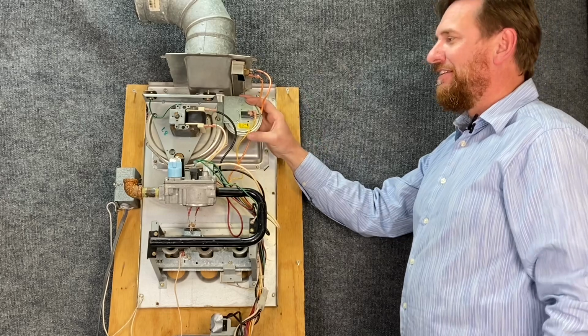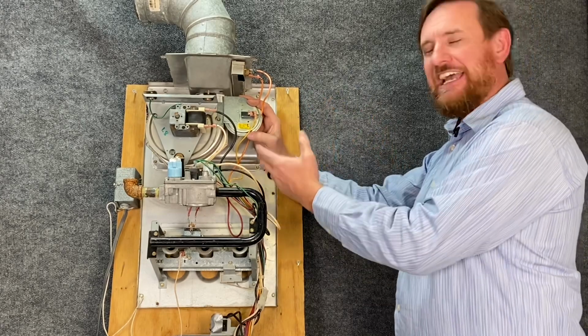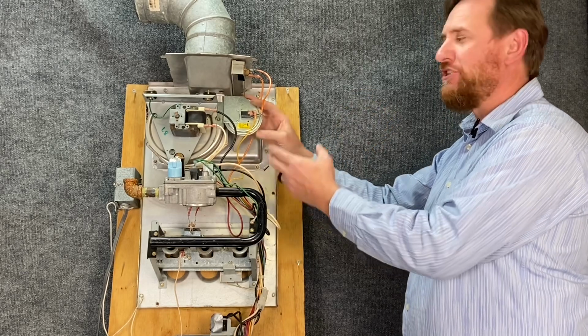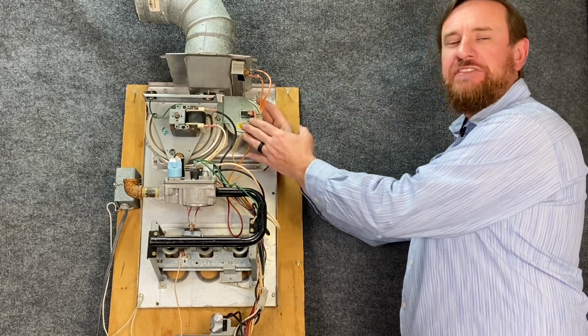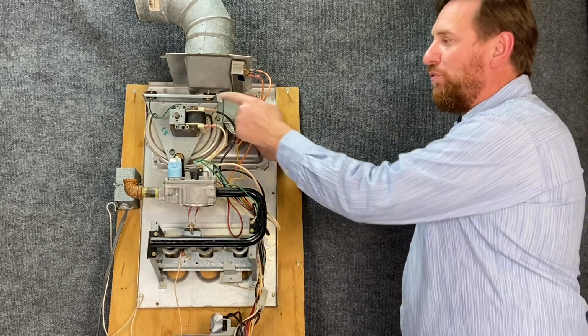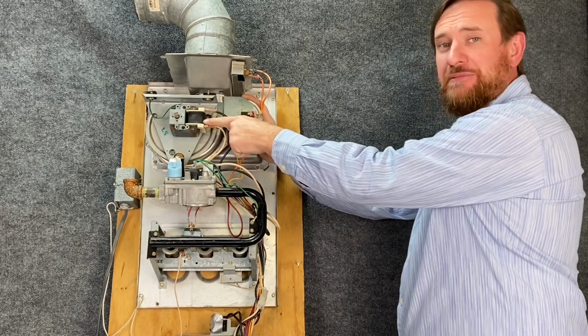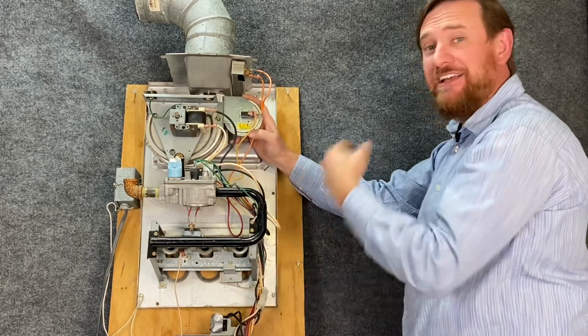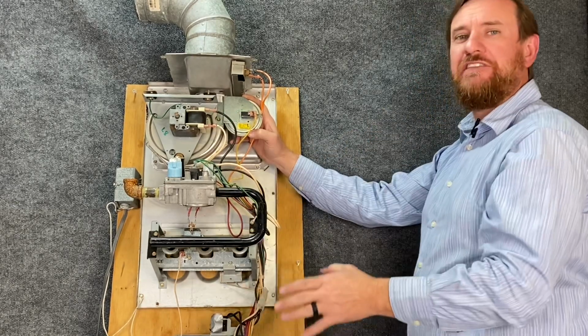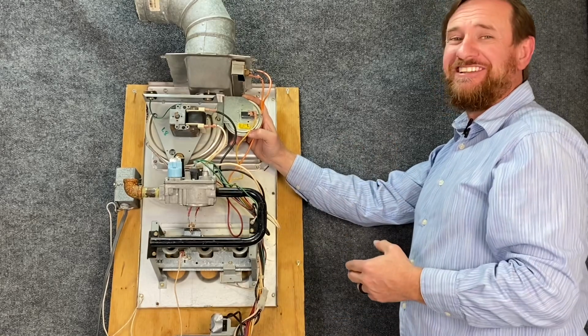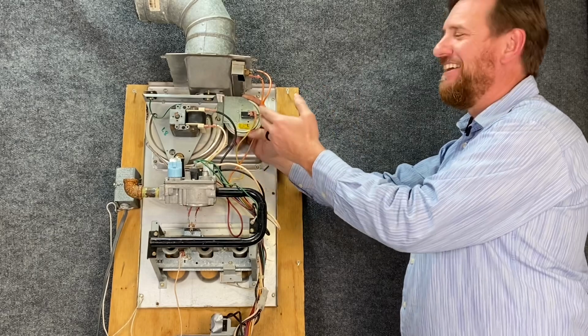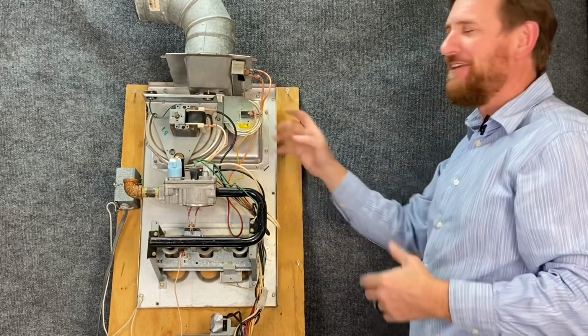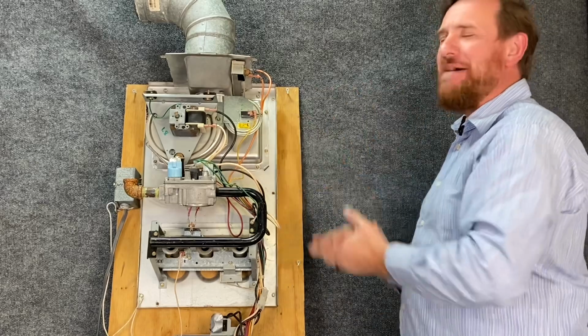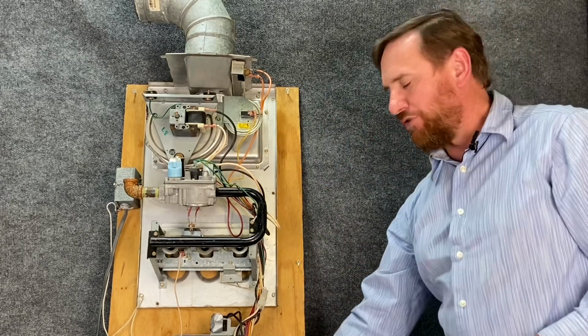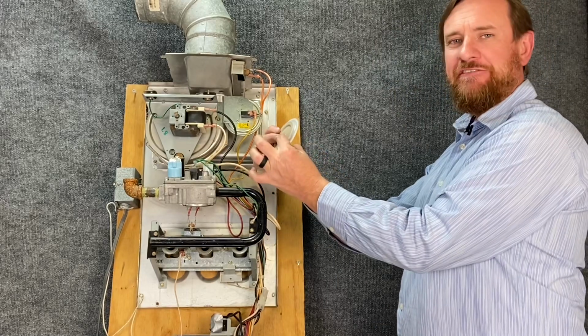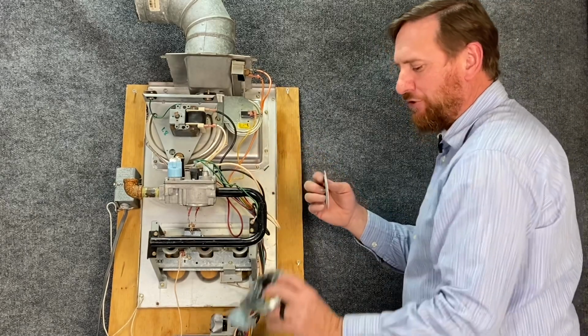To make my students understand, I have them say it as a negative pressure switch or a vacuum pressure switch, so they understand that it's sucking, pulling a draft against the switch. Its job is also to watch this motor, so to speak, to make sure it's doing its job. If this motor stops working, it tells the IFC, hey, we got a problem, and the IFC shuts everything off to make sure we're running safe. Some of my students call it a vacuum pressure snitch because its job is to watch him and snitch if there's a problem. However you need to remember that it's a massively important safety feature. So how it works is quite simple. Inside, there's a type of diaphragm, and there's also a micro switch on one side.